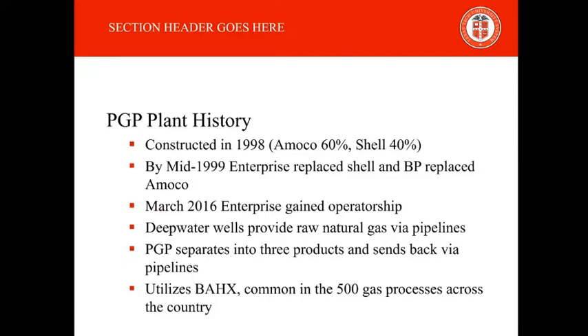So the Pascagoula gas plant operates by pipelines connected to deep water wells, which provide raw natural gas to the plant. Then the plant separates it into three products: a natural gas condensate, a lighter natural gas, and heavier hydrocarbons known as natural gas liquids. And the plant does this by using a cryogenic separation, which utilizes brazed aluminum heat exchangers, which are a very common piece of equipment found in the 500 gas processing cryogenic separations across the country.